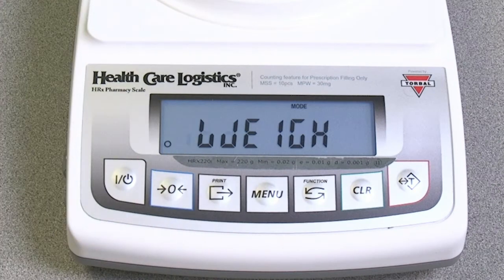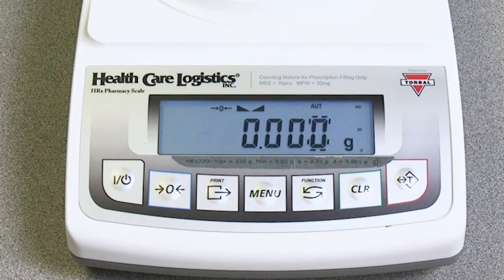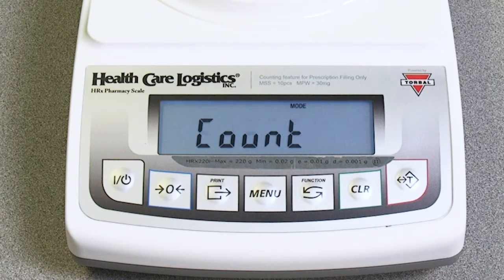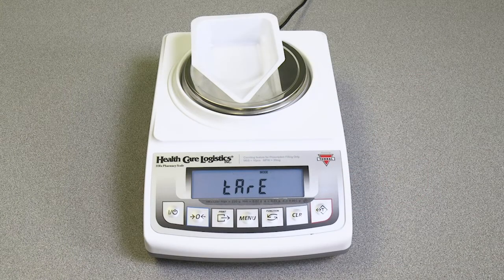To set up the scale to count pills, we need to change the mode from weigh to count. Easy enough to do. Just press the function button until you see the word count. Then press the T key to select. Press tare will now appear on the display. Take the weigh container that you will be using and place it in the center of the pan. After the weight appears on the display and is stabilized, press T once more to tare.